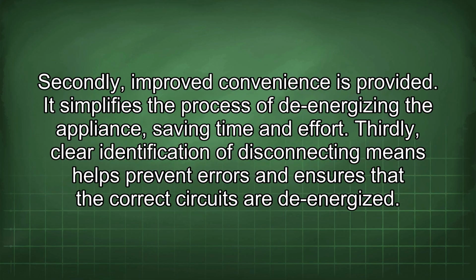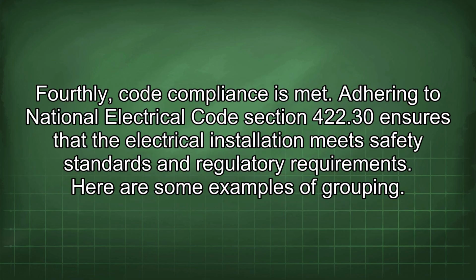Secondly, improved convenience is provided. It simplifies the process of de-energizing the appliance, saving time and effort. Thirdly, clear identification of disconnecting means helps prevent errors and ensures that the correct circuits are de-energized. Fourthly, code compliance is met. Adhering to National Electrical Code Section 422.30 ensures that the electrical installation meets safety standards and regulatory requirements.